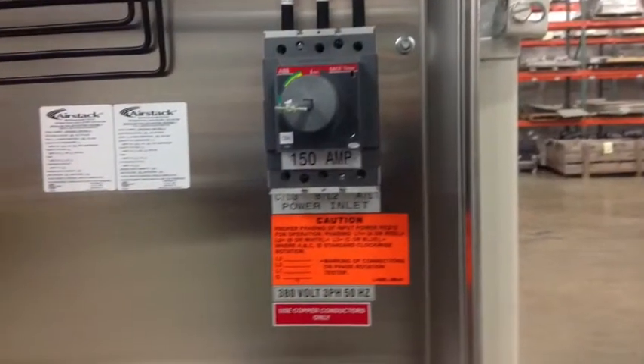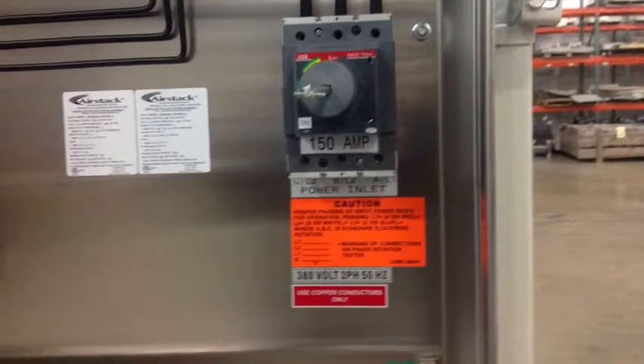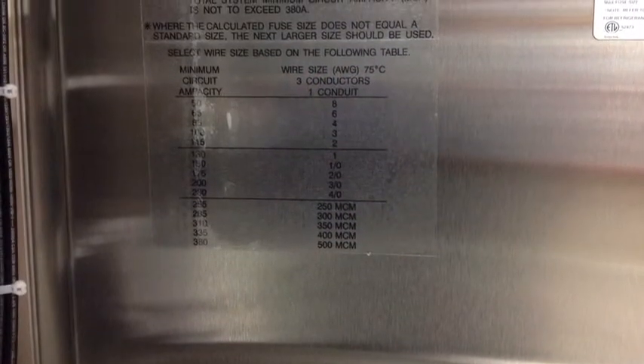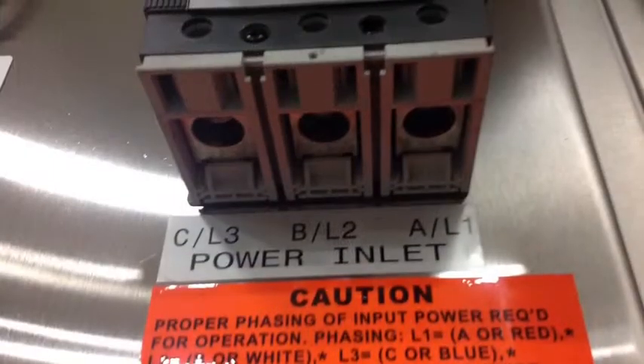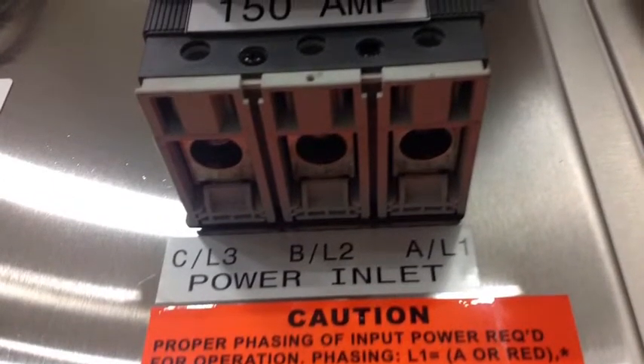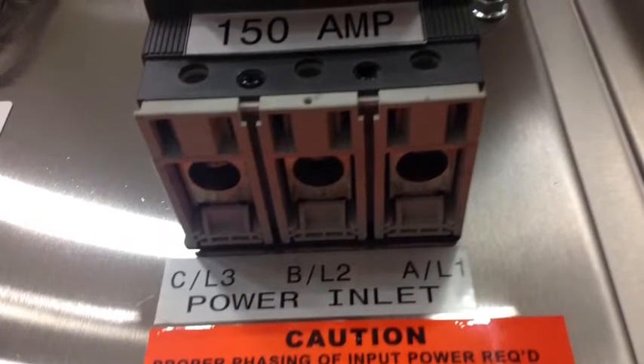And the last little note is that they are single feeds per phase, not parallel feeds. This chart shows that it's 1 aught for the 150 amp breaker, and then just a picture of the bottom of the inlet to the circuit breaker for the 1 aught wire, 1 per phase.